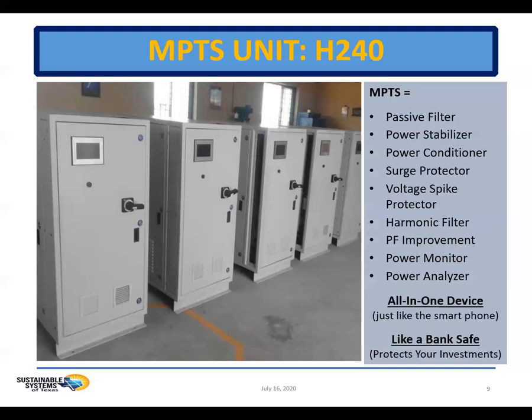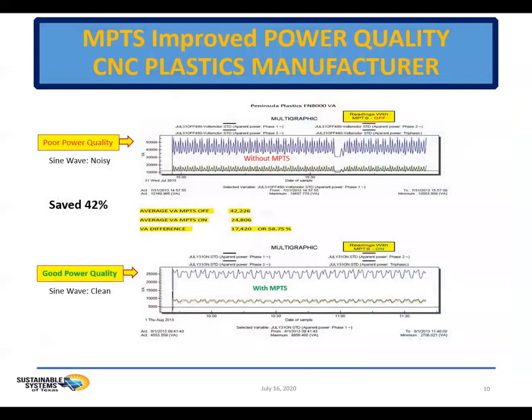It's the lowest impedance device in the electrical network, so it draws the problems to it. The power irregularities in the system flow into the MPTS. The MPTS technology normalizes those irregularities, and then it reintroduces the clean energy back into the network. Your equipment is now protected from further damage. Michael, tell us about these.